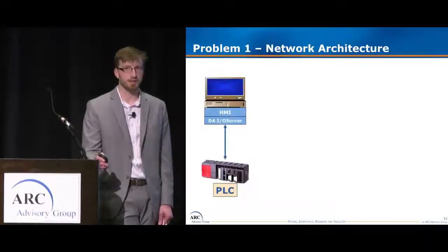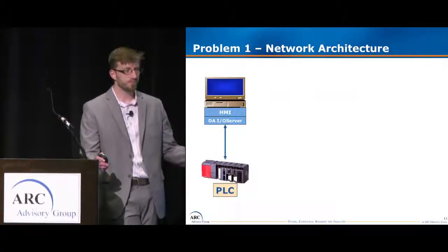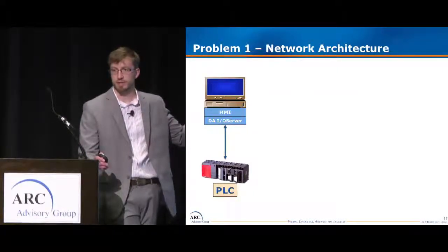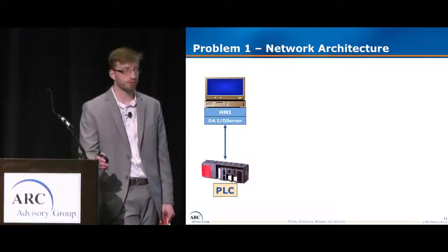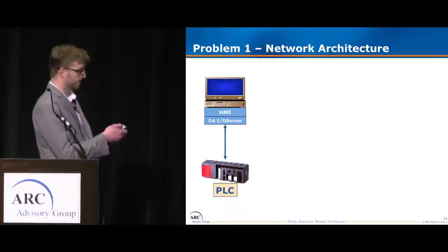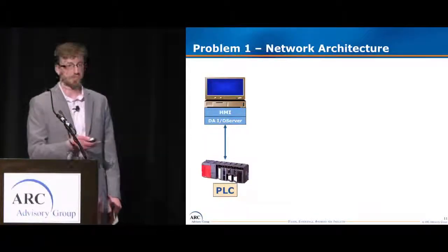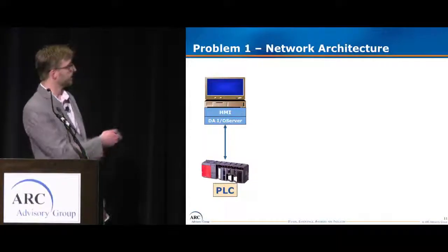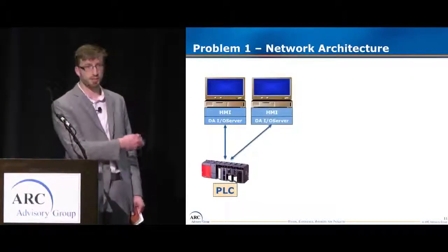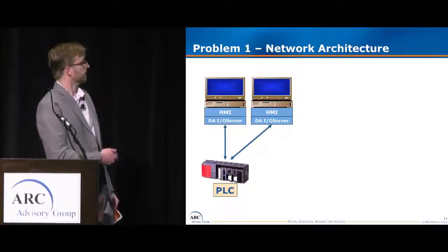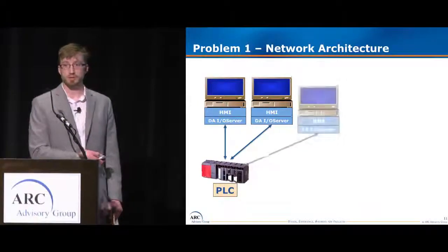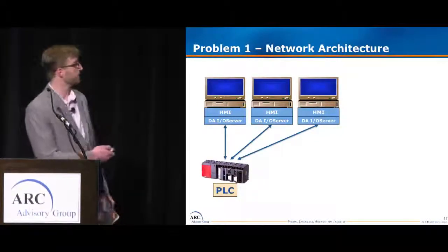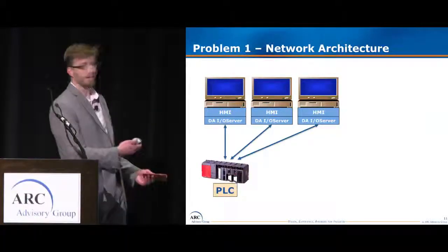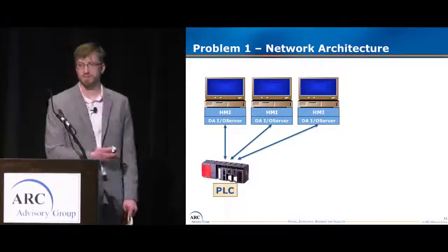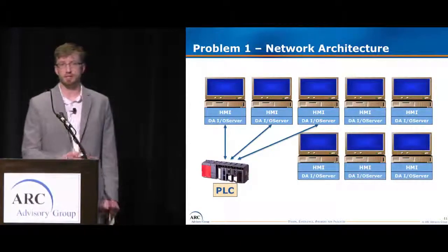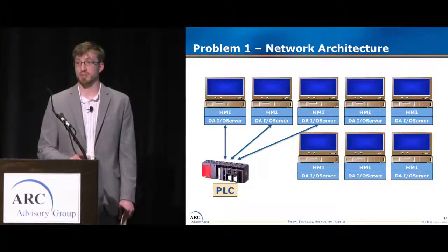So what were these problems with the network architecture? When you have an HMI or SCADA system, you also have an I/O server that communicates to your PLCs or your control systems. And you could add another HMI, and it might have its own I/O server on it as well, and that starts communicating to the PLC and opens up another communication channel. So you start adding these on, and you're adding more load to that communication module on your PLC. It works okay for a few systems. If you have a dozen or 24 of these trying to communicate to a legacy PLC, you start having lots of problems.